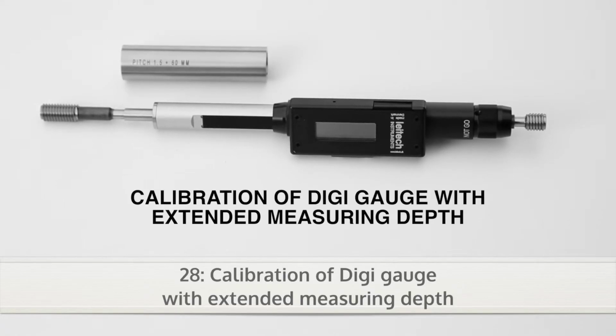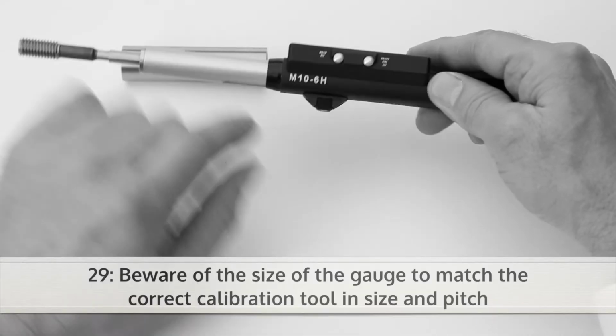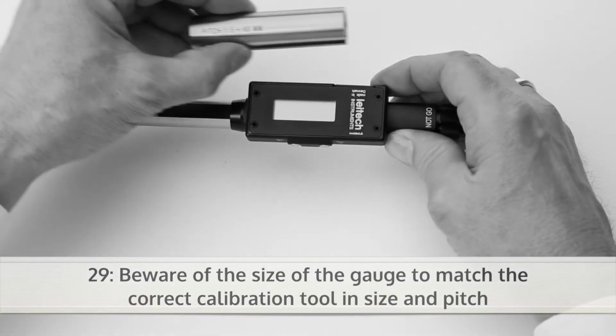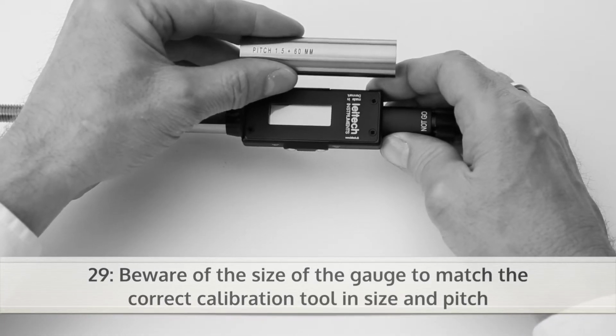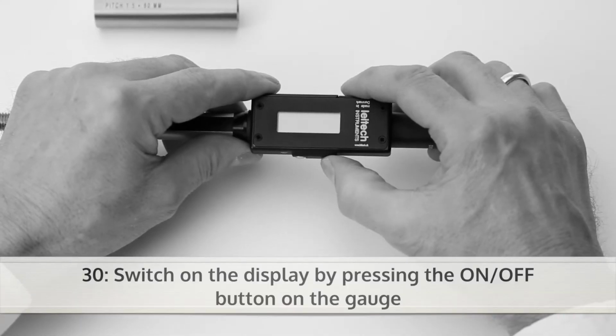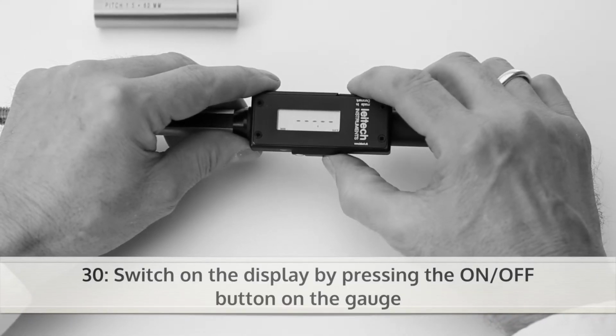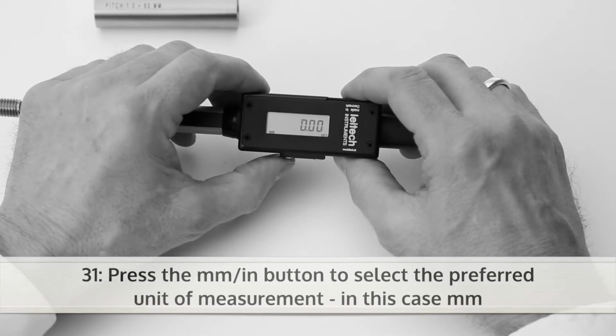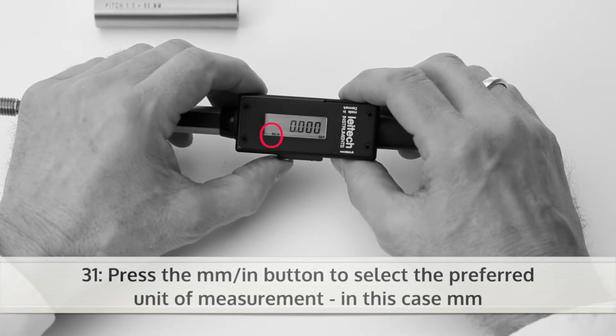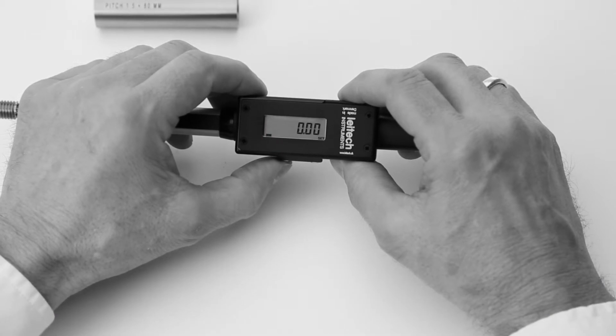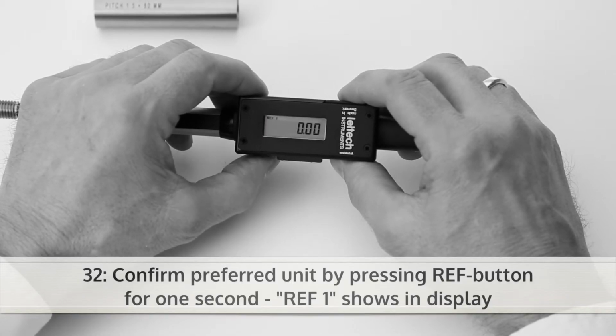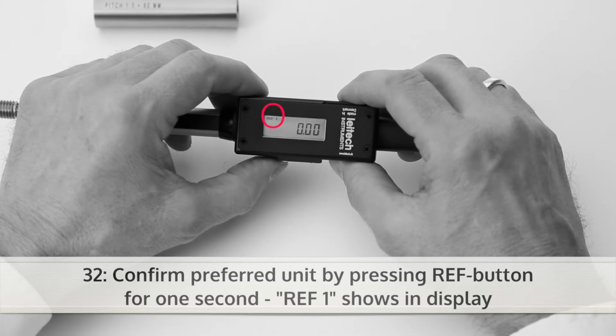Here is how to calibrate a DigiGauge with extended measuring depth. Beware of the size of the gauge to match the correct calibration tool in size and pitch. Now switch on the display by pressing the on/off button on the gauge. Press the mm/inch button to select the preferred unit of measurement, in this case millimeters. Confirm the preferred unit of measurement by pressing Ref button for 1 second. Ref 1 shows in display.